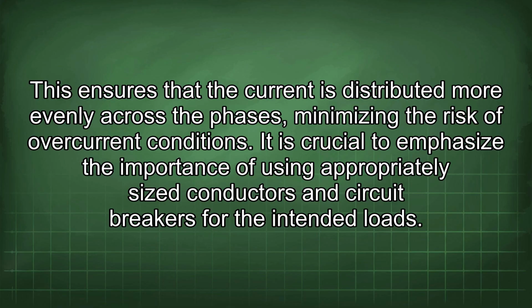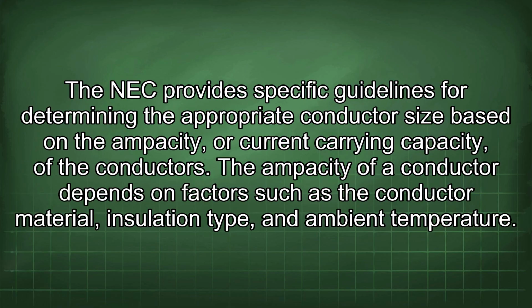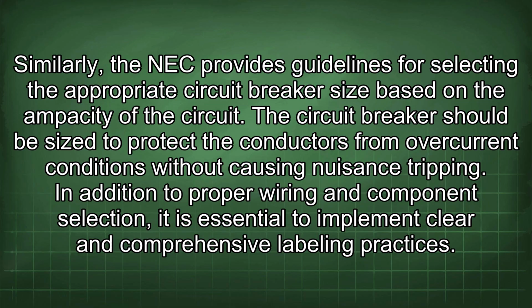It is crucial to emphasize the importance of using appropriately sized conductors and circuit breakers for the intended loads. The NEC provides specific guidelines for determining the appropriate conductor size based on the ampacity or current carrying capacity of the conductors. The ampacity of a conductor depends on factors such as the conductor material, insulation type, and ambient temperature. Similarly, the NEC provides guidelines for selecting the appropriate circuit breaker size based on the ampacity of the circuit. The circuit breaker should be sized to protect the conductors from overcurrent conditions without causing nuisance tripping.